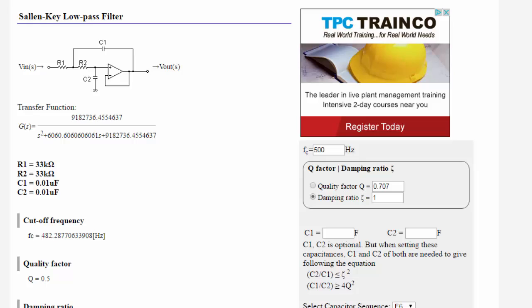What is a low-pass filter? A low-pass filter will pass frequencies below FC hopefully unattenuated, and then anything above FC it starts to attenuate or block those signals. Now why am I picking 500? A filter is not perfect, it's going to have a roll off. I don't want it to start rolling off at 60 Hertz. I want it to roll off farther out. Since I'm really concerned about high frequency noise, I want to pick 500 as a safe area away from 60 Hertz and then anything much higher than 500 Hertz will be blocked.